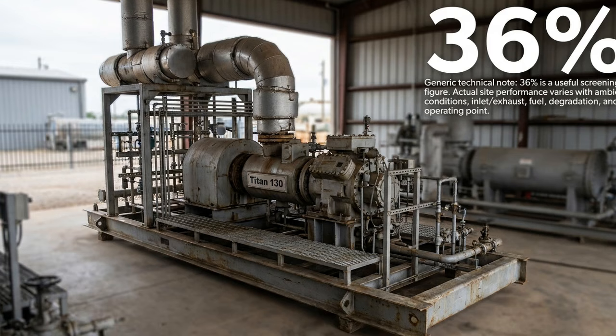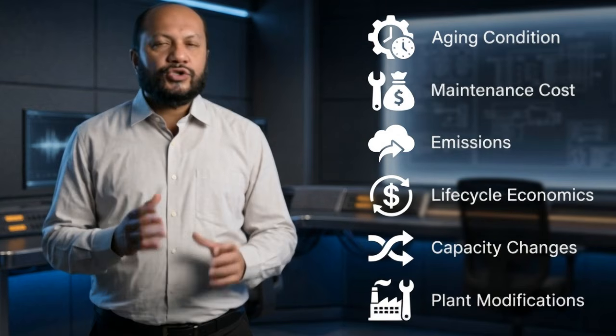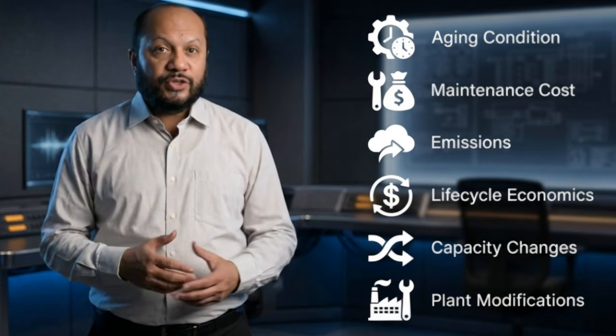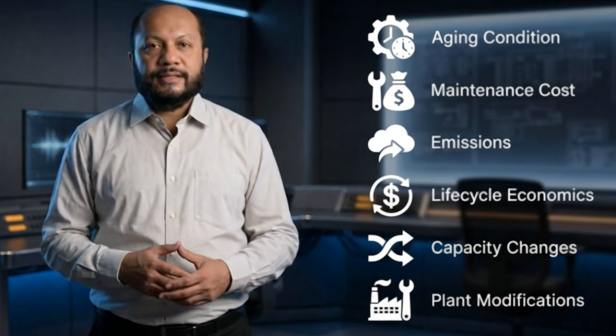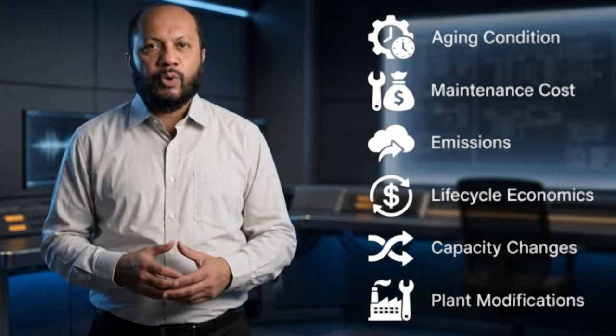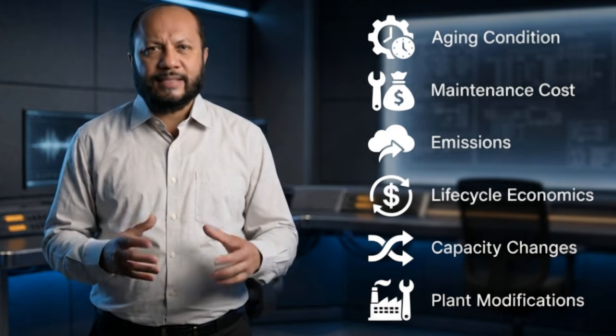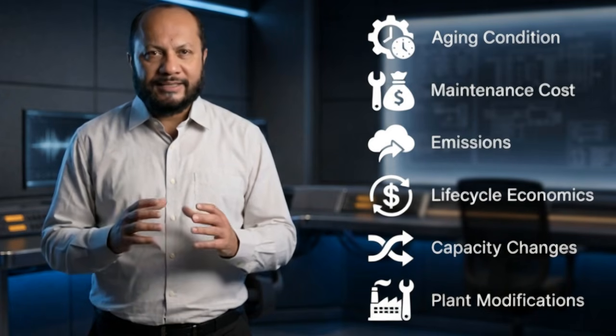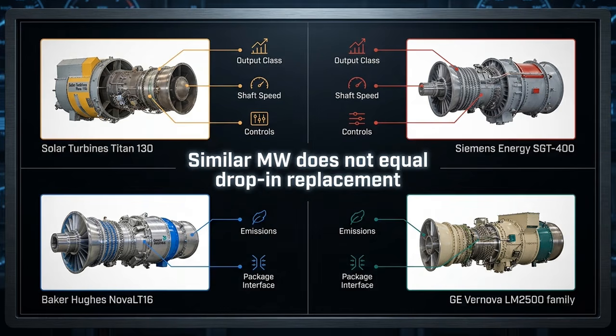That number is useful for screening, but the site result depends on ambient conditions, inlet and exhaust losses, fuel, degradation, and operating point. Replacement discussions usually begin for practical reasons: aging condition, maintenance cost, emissions requirements, life cycle economics, capacity changes, or plant modifications. But a turbine replacement is never just an engine swap. It is an integrated system decision. A critical warning: similar megawatts do not mean a direct drop-in replacement. Titan 130, Nova 16, SGT 400, and LM2500 family equipment must be compared using verified model data, package interfaces, shaft speed controls, emissions, and site rating.